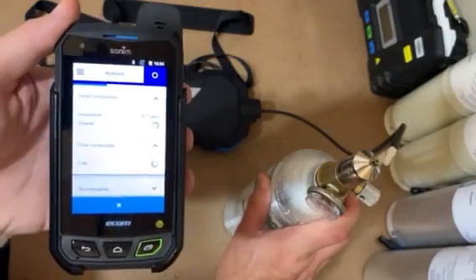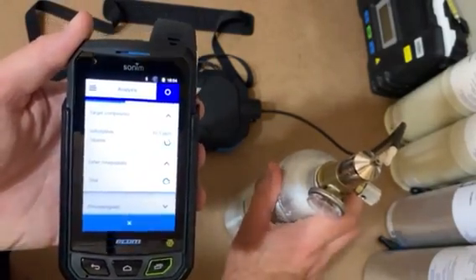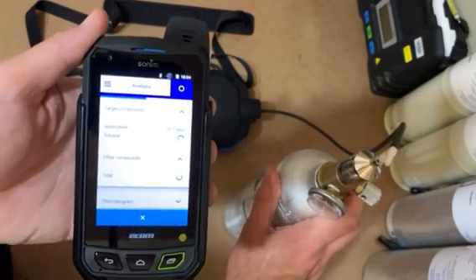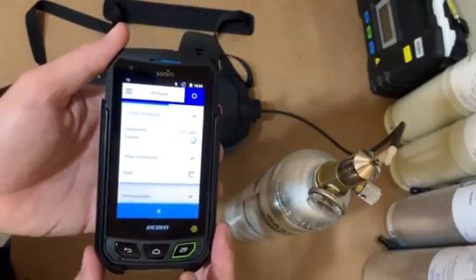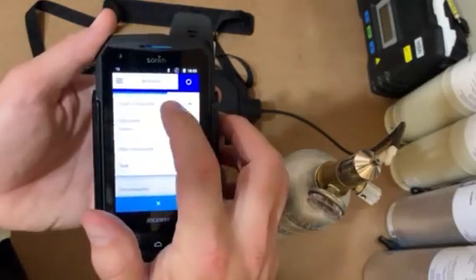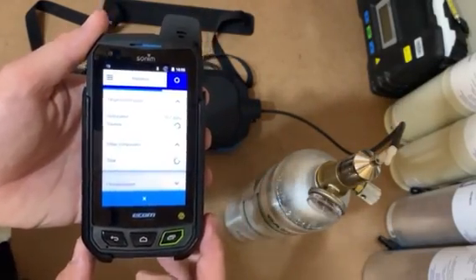If you're looking for benzene, styrene, or xylene, you only ever use this calibration gas. It's got about another 30 seconds, but to save everybody time, that's how you do it. Once it's done, you see this progression bar up here — it'll ask you if you want to save it or discard it. And that's it. Thank you very much.